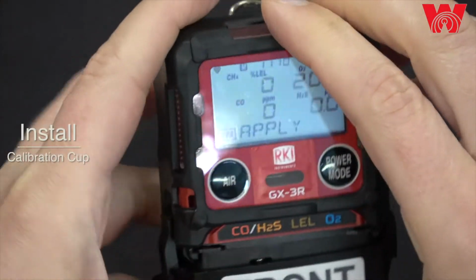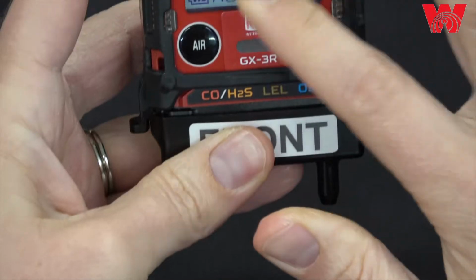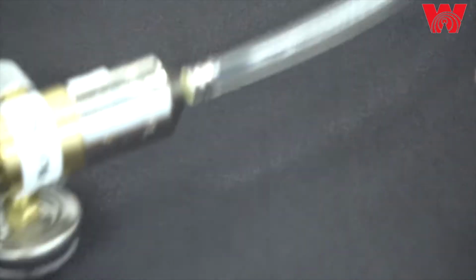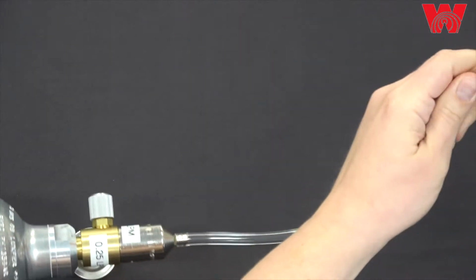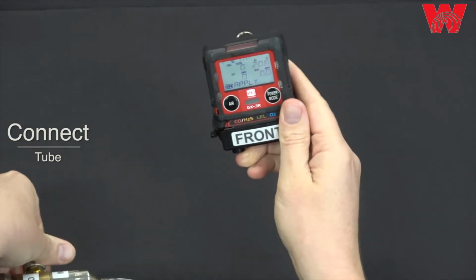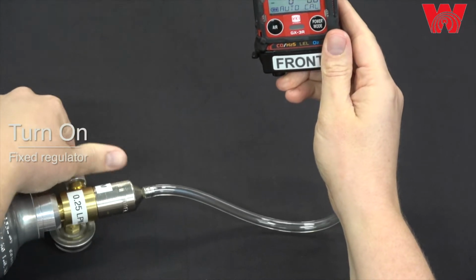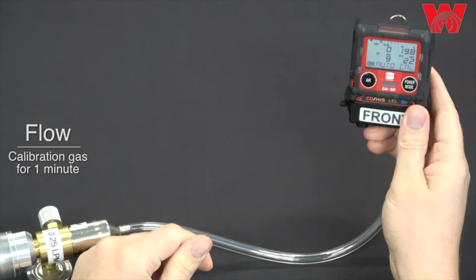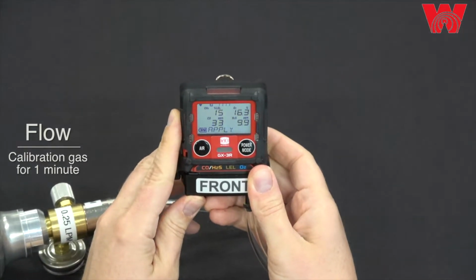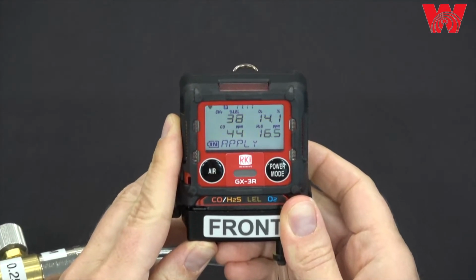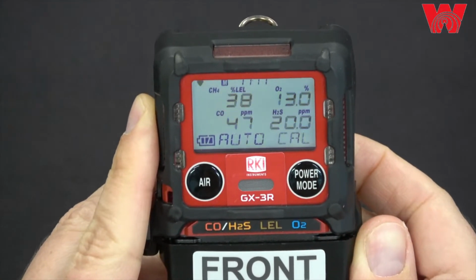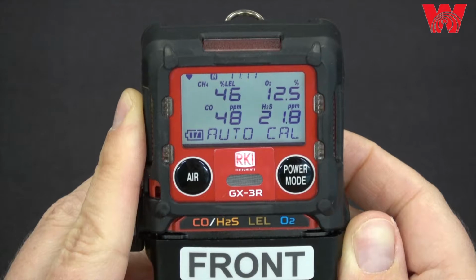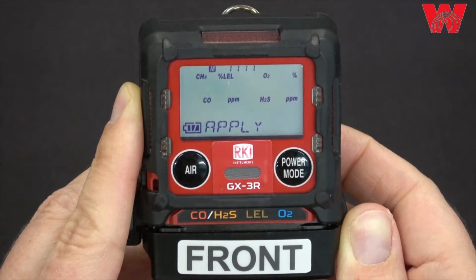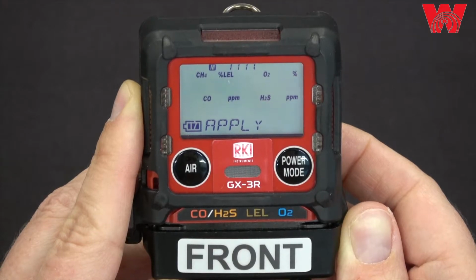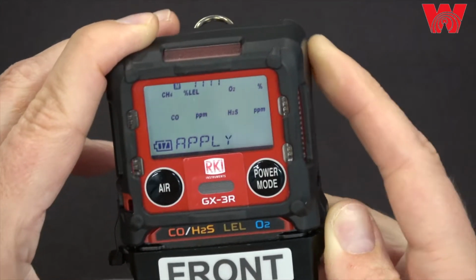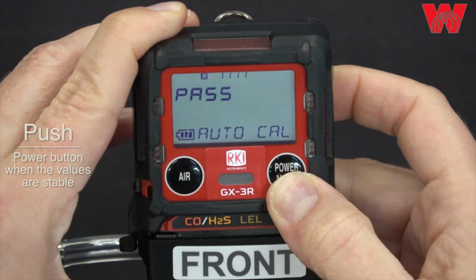Install your calibration cup. There is a label that says front, and it needs to face the LCD. Connect my tubing and turn my regulator on. Gas needs to flow for 1 minute. You can see the readings starting to get stable. Okay, and then press power mode to perform the calibration.